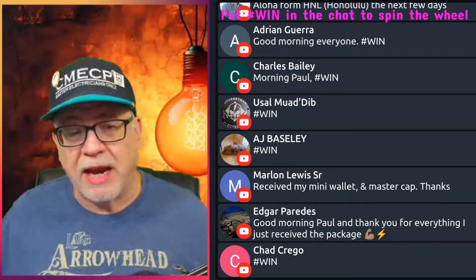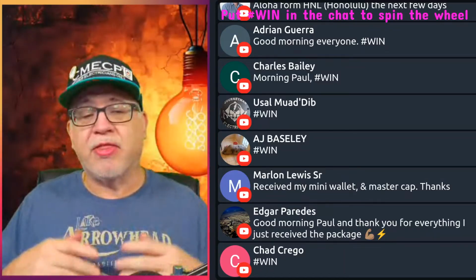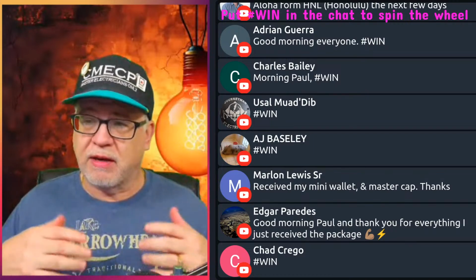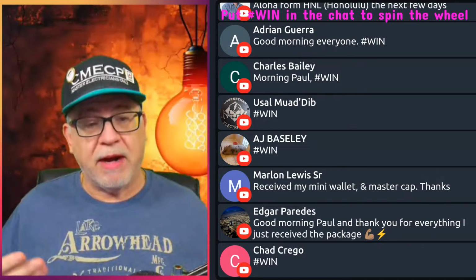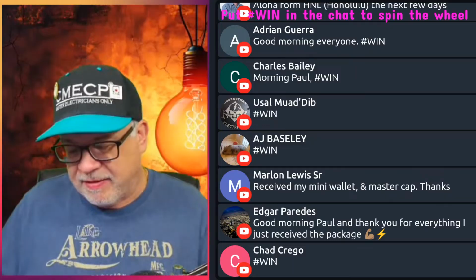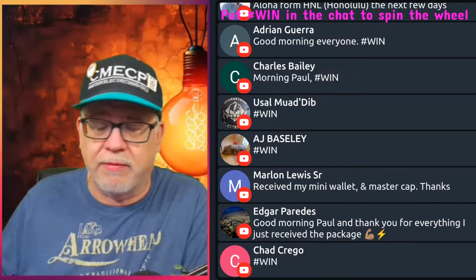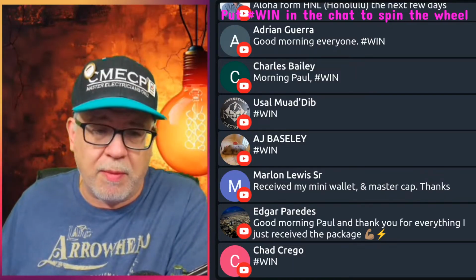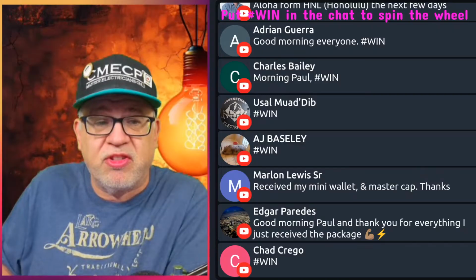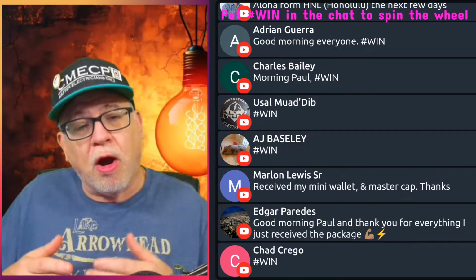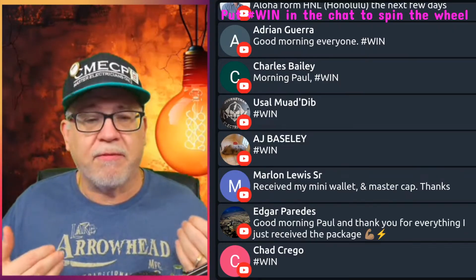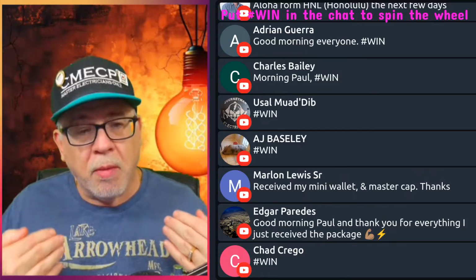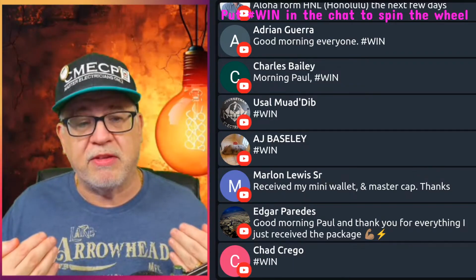So some things were added. For example, 120.13 will be added in order to clarify the minimum number of branch circuits that you're required to have. Now that's not going to take the place of the small appliance branch circuit requirement either, that stays a certain number, minimum of 2, and the laundry. But we are going to get direction to clarify the minimum number of general use branch circuits, okay.